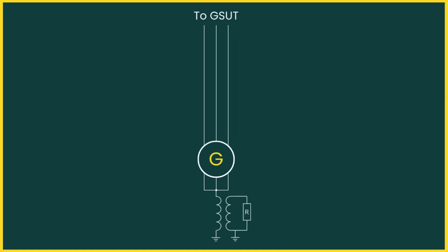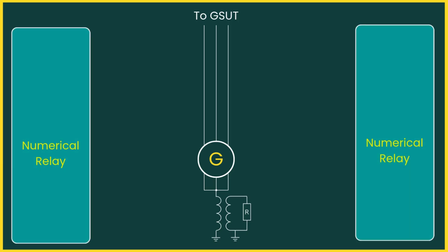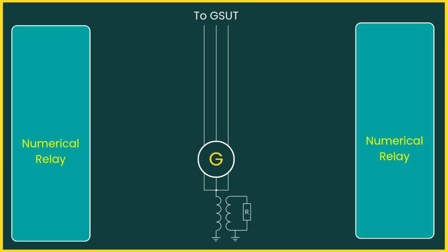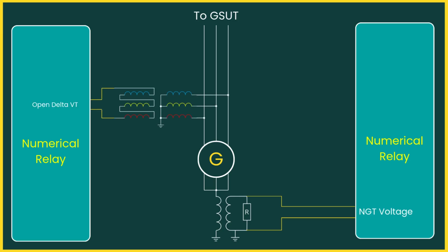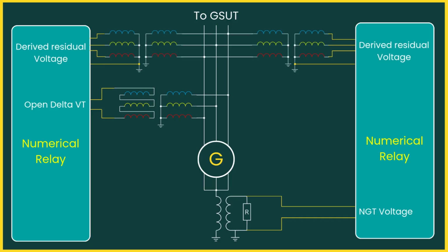In actual generator protection systems, the 95% Stator Earth Fault Protection is implemented using 2 redundant numerical relays for high reliability. Here's how it's typically configured. One relay measures the neutral displacement voltage directly across the NGR through the NGT secondary. The other relay measures the residual voltage across the open delta VT connection. The derived voltage method can be implemented in both relays, since all 3-phase voltages are already available in each relay for other protection functions. This provides redundancy and improves reliability of earth fault detection.